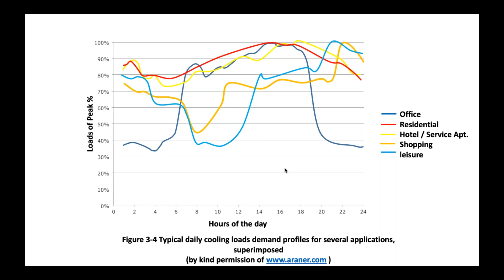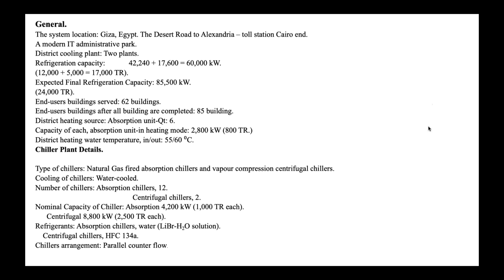Now, the case for Egypt — I've chosen the first district cooling plant built in Egypt: a district cooling and heating system in Smart Village, located in Giza near the pyramids. It's a plant with 24,000 tons of cooling. In this plant we used two different types of cooling systems: one is an absorption system operating with natural gas, and the other operates with electricity. This is because the cost of electricity and gas at the time the plant was built was varying constantly. So we have 12 absorption chillers and 2 centrifugal chillers.